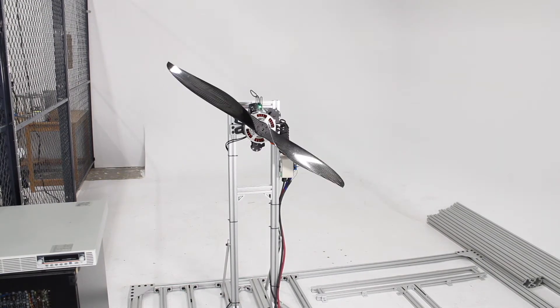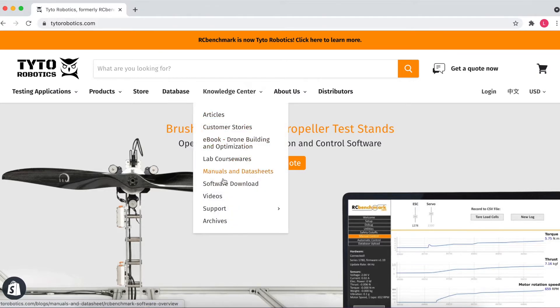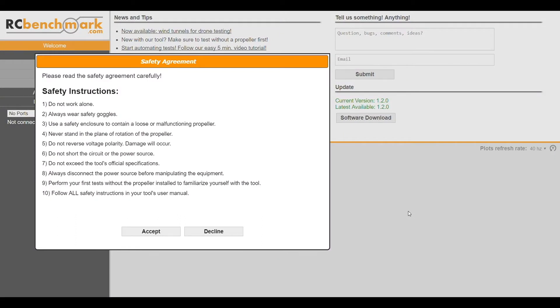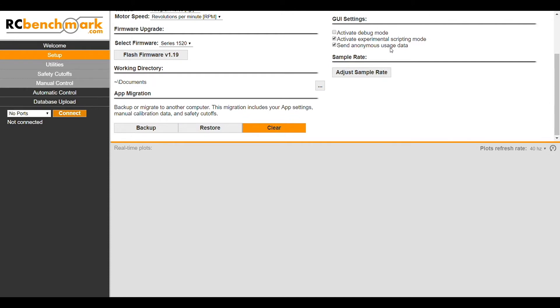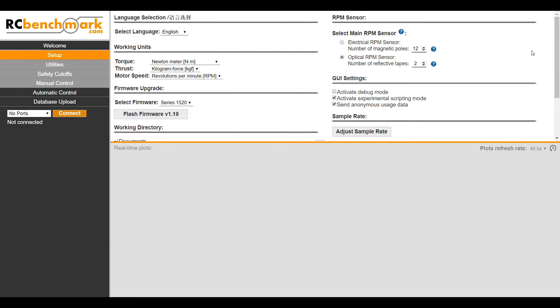Now that our system is all set up, it's time to run some propulsion tests. The first thing we have to do is download the RCbenchmark software, which we can do on the Tyto Robotics website. We'll head on over to Knowledge Center, then Software Download, and download the most recent version. We'll quickly go through the installation instructions, then head over to our desktop where we'll find the program, open it up, and accept the safety agreement to get started. The first thing we'll do is head on over to Setup, where we'll put in our working directory — here it's set up as Documents, which is just fine. Then we'll enter in the number of pieces of reflective tape that we put on our motor, so our optical sensor knows how to measure our RPM.